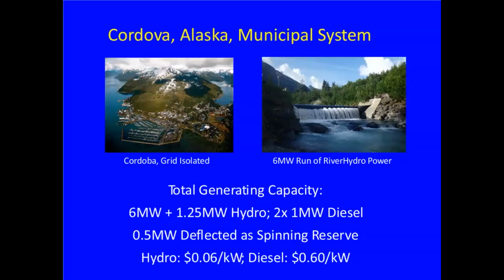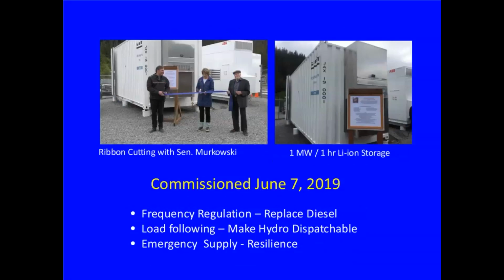So the hydropower had to be backed up with considerable diesel, and about half a megawatt was deflected as spinning reserve. What we did is suggest putting in a megawatt of storage. You can see the ribbon cutting here, and this is the unit as it sits there. This will do frequency regulation, virtually replacing the diesel.